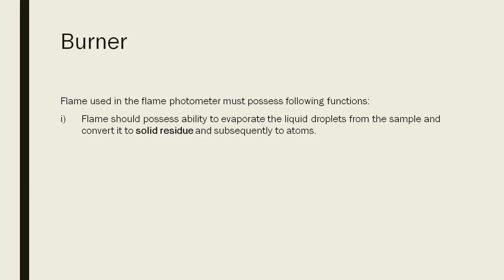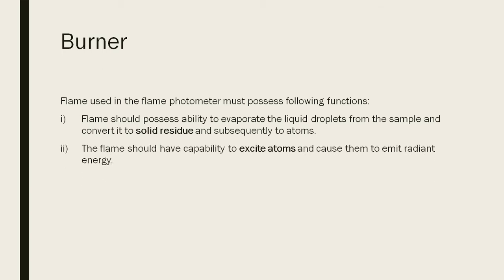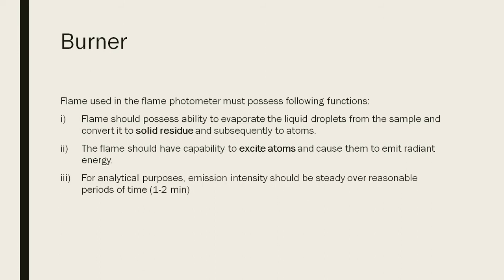It should have the ability to evaporate the liquid droplets from the sample and convert them into solid residue and subsequently to atoms. The flame should have the capability to excite atoms and cause them to emit radiant energy. For analytical purposes, the emission intensity should be steady over a reasonable period of time, that is 1 to 2 minutes.